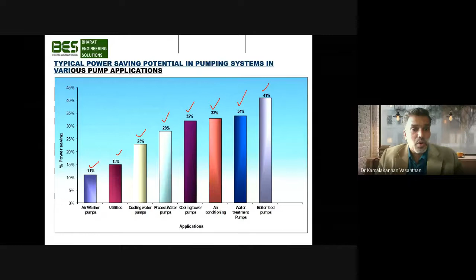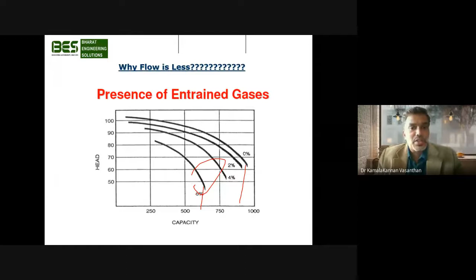And some people will be surprised when there is a sudden reduction of flow. We noticed in certain sites, when there was presence of entrained gases, even up to 4, if you take an example of 6% here, the flow dropped from a maximum of 900 meter cube to almost 600 meter cube with the presence of 6% entrained gases. Almost 300 meter cube of flow is reduced. So we need to ensure that there is no presence of entrained gases in our system.